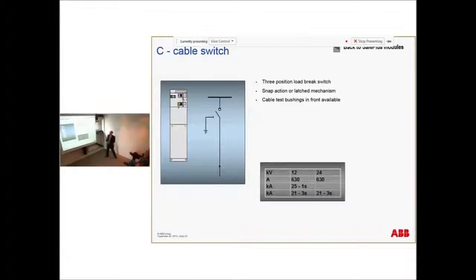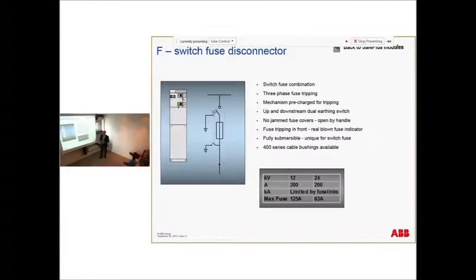I mentioned this switch is with SF6 gas, so it's connected. You open it with this mechanism, and you earth it with the same mechanism, and everything is mechanically interlocked. So there is personal safety in this interlock. And all the switches have mechanical interlock. Also for the fuse one, if the fuse is blown, you need to open, you need to earth in order to open the cover to remove the fuse.